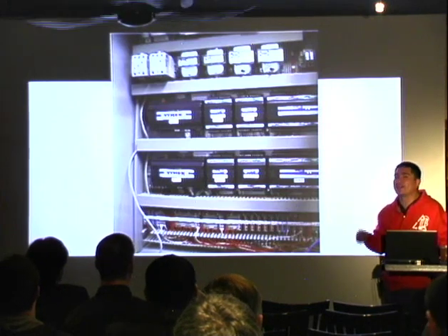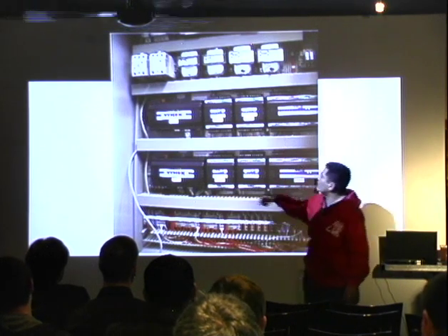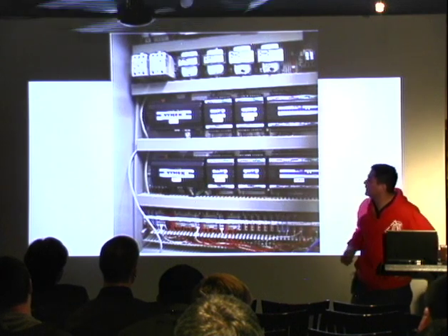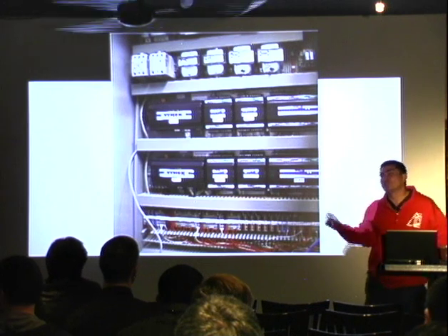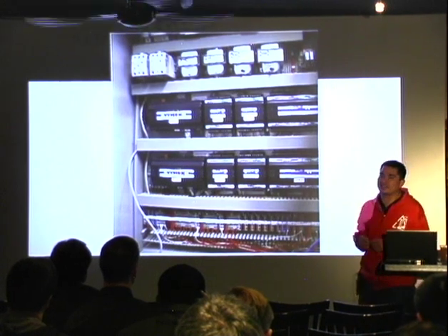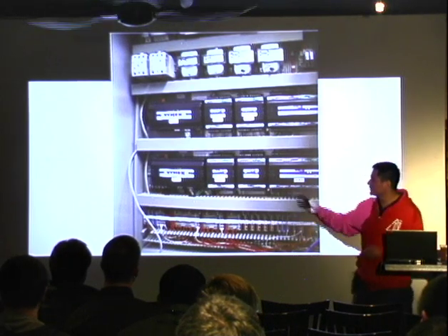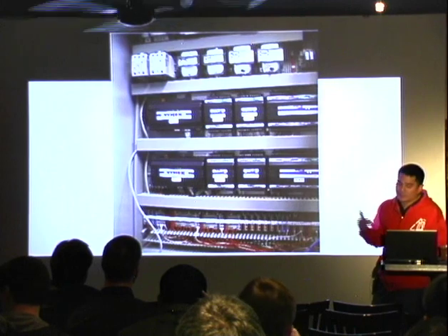If you go to an actual Fortune 500 and see how this is deployed, you'll find a cabinet somewhere. A lot of these machines are Tridium devices — they're just plugged in and tucked away. This is where they hook into the devices and run power and all that. There's a network cable somewhere connecting it to the network. Some people say this is segregation — you cannot get to the device from the network. But that's actually not true. If you know where these are on the network, you can get to them and then get to the downstream devices.